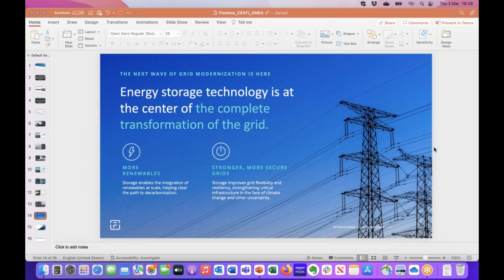The ones where it gets interesting are particularly when you're on microgrid islands, looking at black start capabilities and others. For certain projects it's expensive, but for those high advanced functionality cases, they actually get tested in the field or in the lab, running simulations and doing it with the hardware. Often the utility will come and check those tests, and it becomes a pre-requirement to deploy on the grid, so you catch some issues before they get deployed. That only tends to happen for those high or challenging applications that have a lot more interaction with other parts of the system.